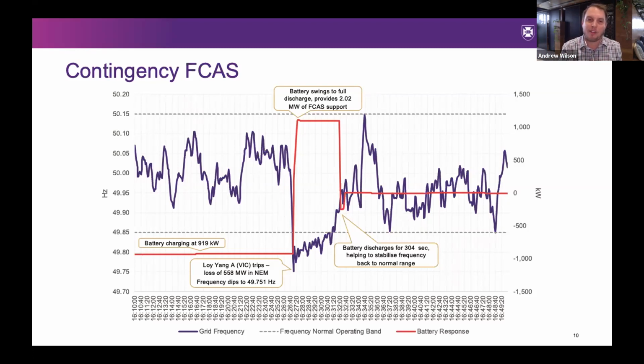On this particular afternoon, we were charging at about 900 kilowatts for arbitrage reasons, getting ready ahead of a forecast price spike, and then all of a sudden that event happened. The battery was able to not only start fully discharging, but to swing between those two modes very fast and provide actually 2 megawatts worth of support to the network, even though the rated capacity of the battery is only 1 megawatt.